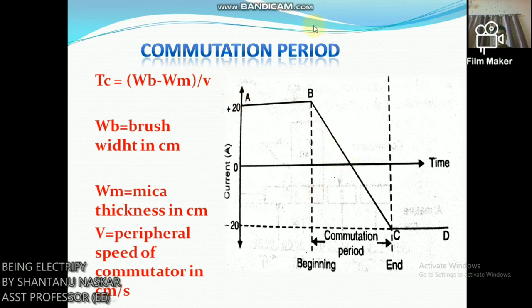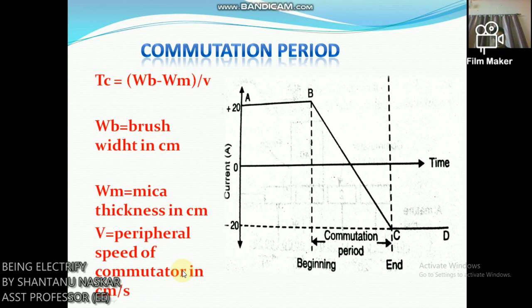The commutation period is given by: Tc = (Wb − Wm) / v, where Wb is the brush width in cm, Wm is the mica thickness in cm, and v is the peripheral speed of the commutator in cm per second. When a coil undergoes commutation, two commutator segments remain short-circuited by the brush. Therefore, the commutation period Tc equals the time required for the commutator to move a distance equal to the brush width minus the thickness of one insulating mica strip.